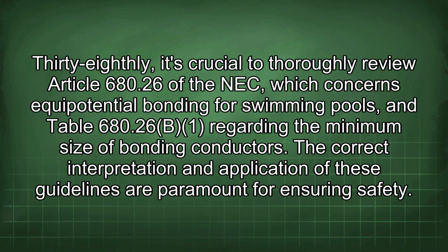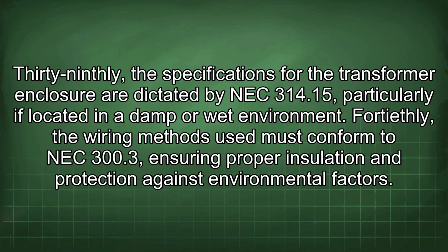38thly, it's crucial to thoroughly review Article 680.26 of the NEC, which concerns equipotential bonding for swimming pools, and Table 680.26 regarding the minimum size of bonding conductors. The correct interpretation and application of these guidelines are paramount for ensuring safety. 39thly, the specifications for the transformer enclosure are dictated by NEC 314.15, particularly if located in a damp or wet environment.